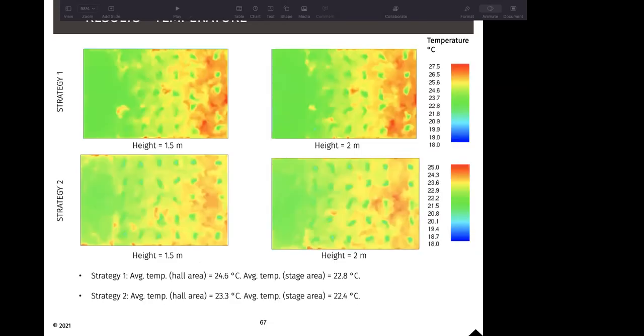Why that was done was because looking at strategy 1 for the heat load provided, we can see that at 1.5 meter height and 2 meter height, at the back of the hall, because there were only 2 return risers, the supply air was not moving towards the back of the hall as much, and there was heat being accumulated. The temperature was rising as high as 27.5 degrees. Whereas in strategy 2, because we have increased the CFM as well as provided more return risers at the back of the hall, the peak temperature at the back is around 24 degrees. We can also see that the average temperature for strategy 1 is 24.6 degrees, and the average temperature for strategy 2 is 23.3 degrees. So we were able to decrease the temperature by 1.3 degrees.